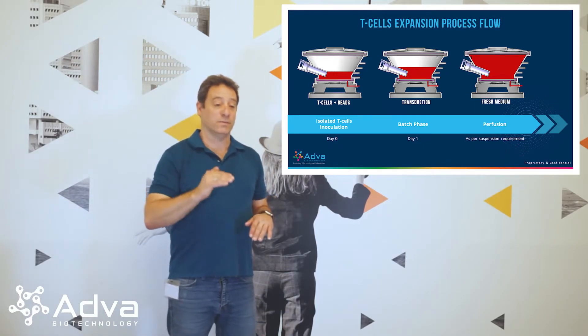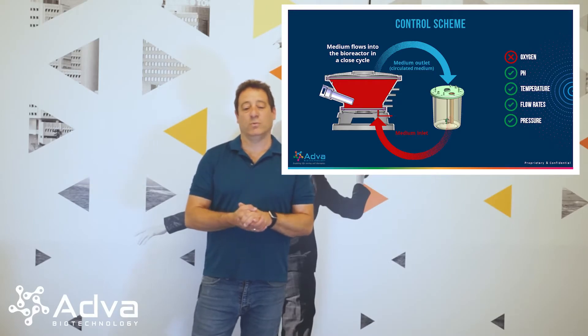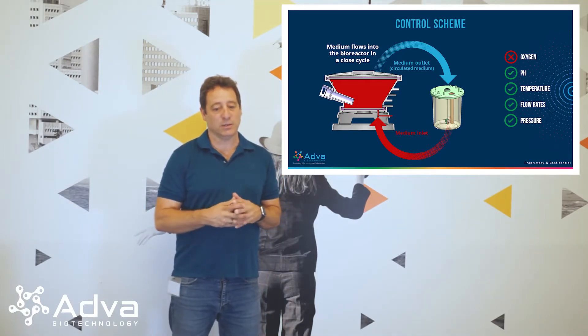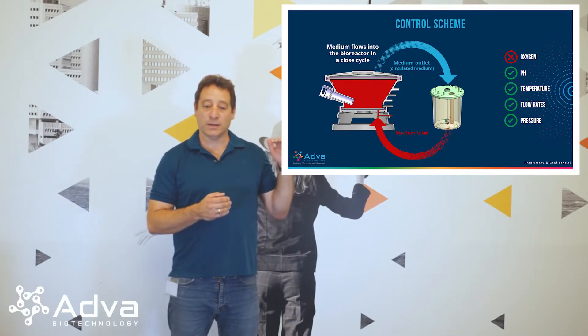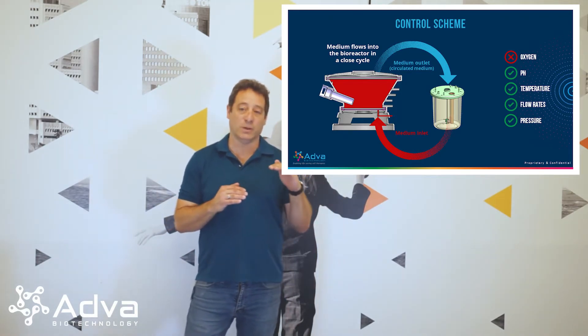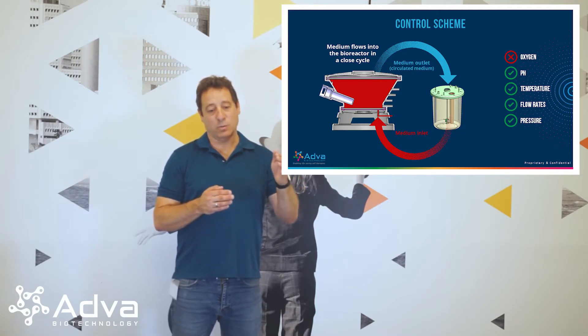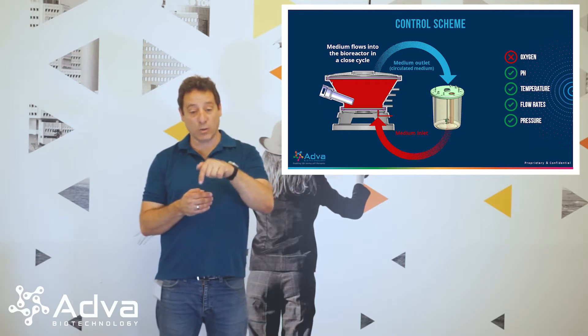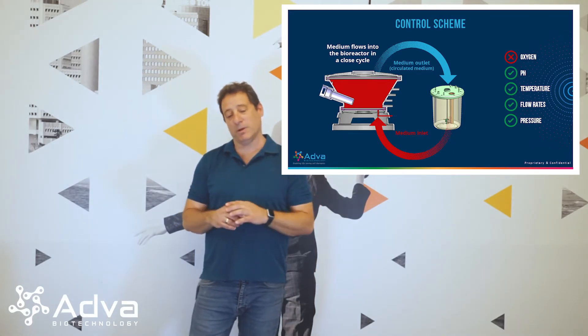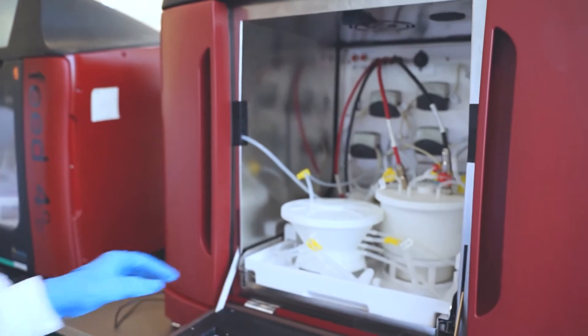The third mode begins once the cone is full — we switch into perfusion. The reservoir or conditioning chamber is intended to condition the media. For example, we put the media at 100% oxygen, while in the cone itself we want 50%. Once the oxygen level in that cone drops below 50%, we have a recirculation: fresh media with 100% oxygen comes into the cone, and waste media with less than 50% oxygen comes out, goes into the conditioning chamber, is conditioned again, and recycled.